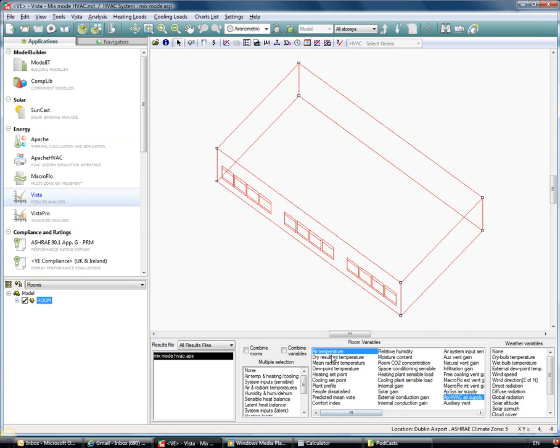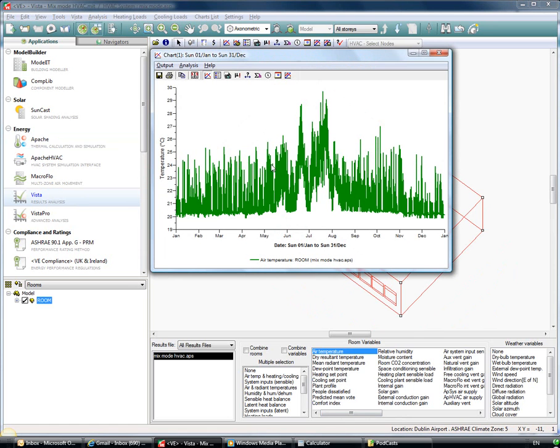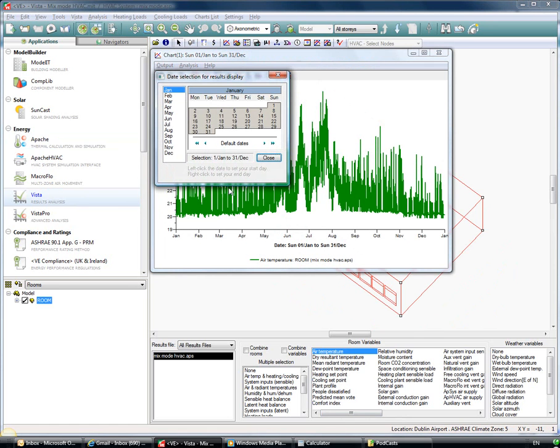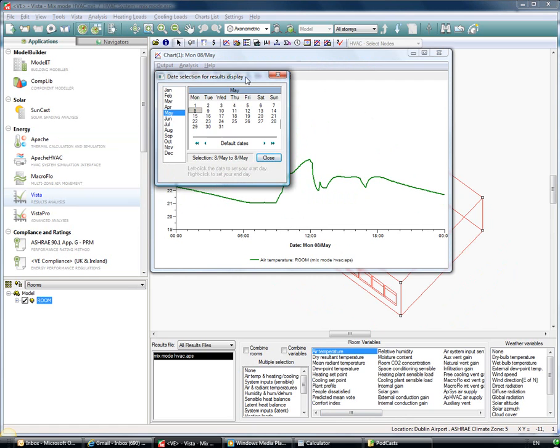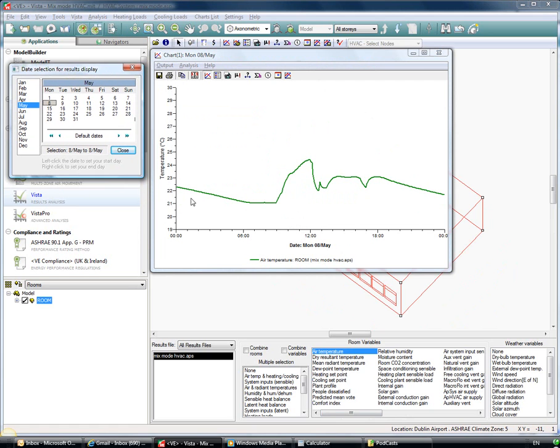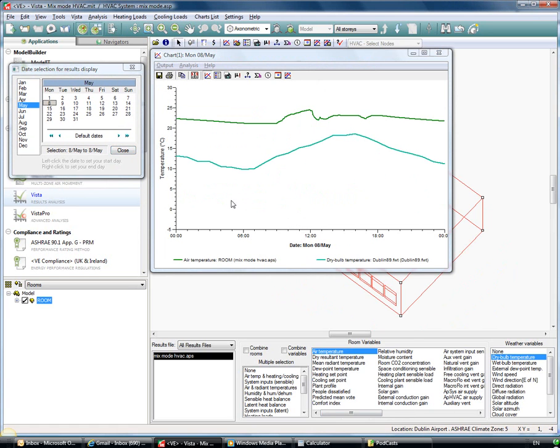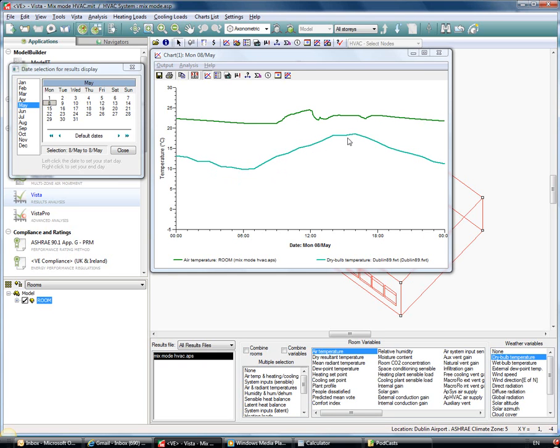We can look at air temperature in the space and we can choose a particular day, so we may choose May the 8th. And as I look at May the 8th, I can see the dry bulb temperature outside. And so once that dry bulb temperature between the hours of 8 and 5 is below 16 degrees, our mechanical ventilation system should be on. And once it goes above 16 degrees outside, then our mechanical ventilation system should be off and our natural ventilation system should be on.